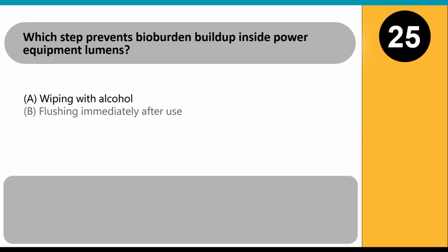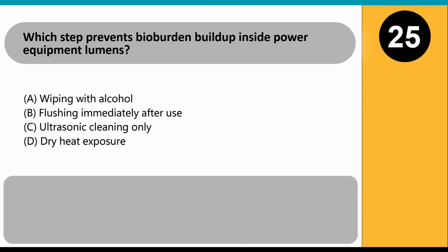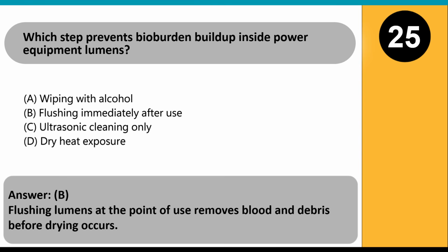Which step prevents bioburden buildup inside power equipment lumens? A. Wiping with alcohol. B. Flushing immediately after use. C. Ultrasonic cleaning only. D. Dry heat exposure. Answer: B. Flushing lumens at the point of use removes blood and debris before drying occurs.